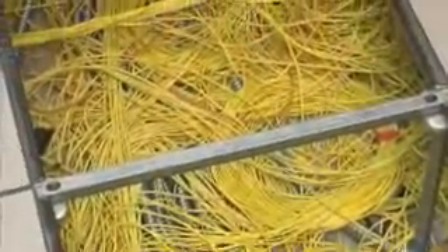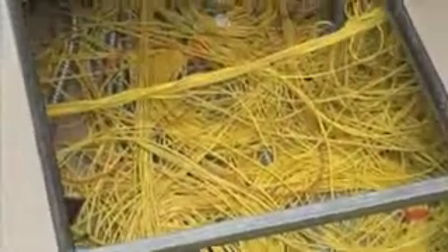Once we started looking into the floor itself, underneath the raised floor, the cables, we had run the cables across the cold air coming from the cooling unit in the room, so we were actually blocking the air that we needed to get to the front of the machines.